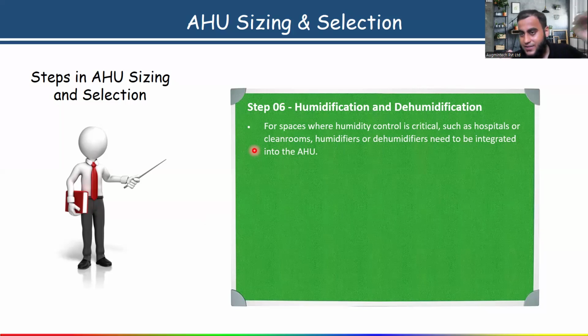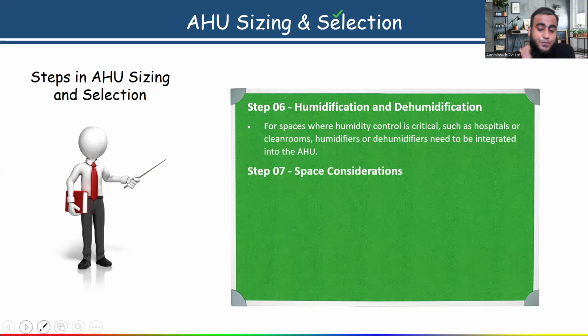Then filter selection I have also discussed: MERV, the different types of rating filter, and which type of filter you have to use. After that, in the fifth step, I think we discussed the fan selection also. For that, our main target is external static pressure, because based on static pressure and airflow rate, with the help of different catalogs, you will get the different model numbers and sizes of fan. The next step, step 6, is humidification and dehumidification. How to select and size the humidifier and dehumidifier, the selection criteria, I have also discussed with you. Now the next step is space consideration. Remember, these are some details which we have to submit to the manufacturer for the AHU.